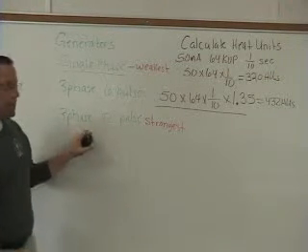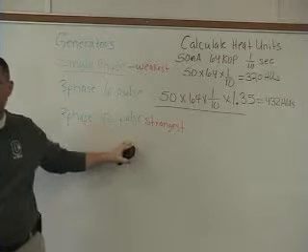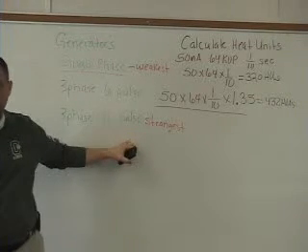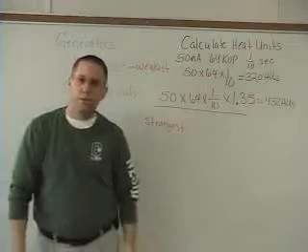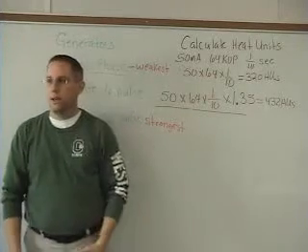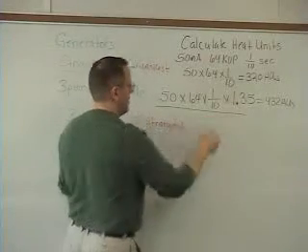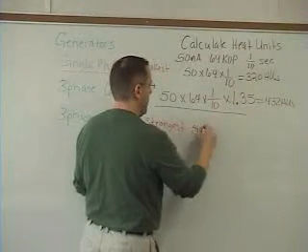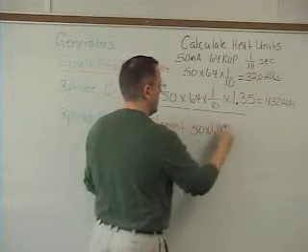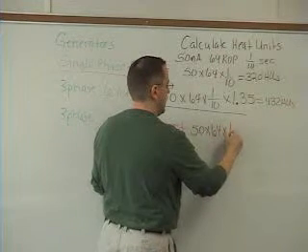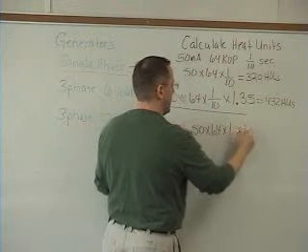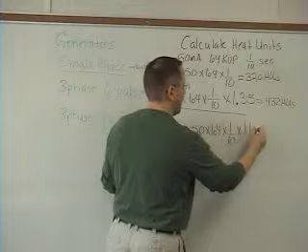Now, these are going to be word problems, so it'll tell you that it's a single phase, or a 3-phase 6-pulse, or a 3-phase 12-pulse. If it tells you it's a 3-phase 12-pulse, we're going to change this number. We're still going to do the 50 mA times the 64 kVp times the 1/10 times 1.41.